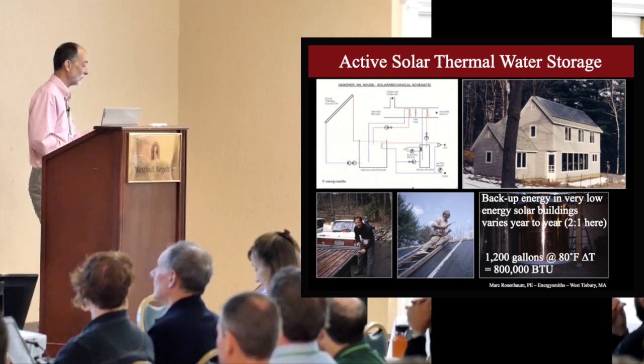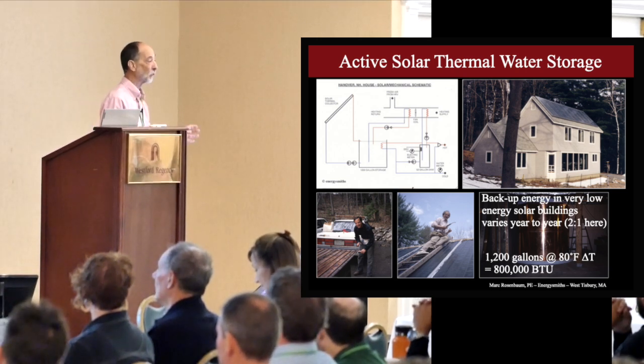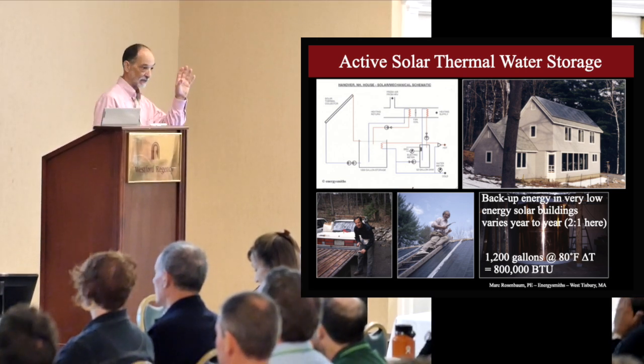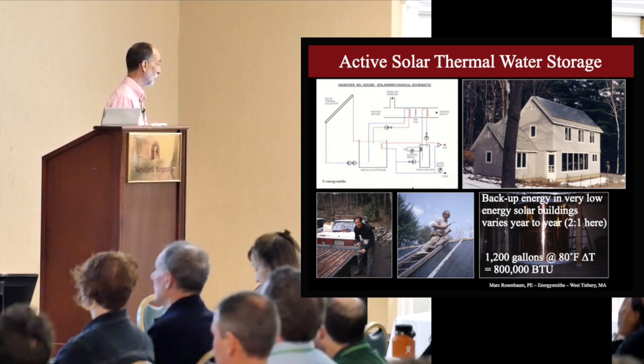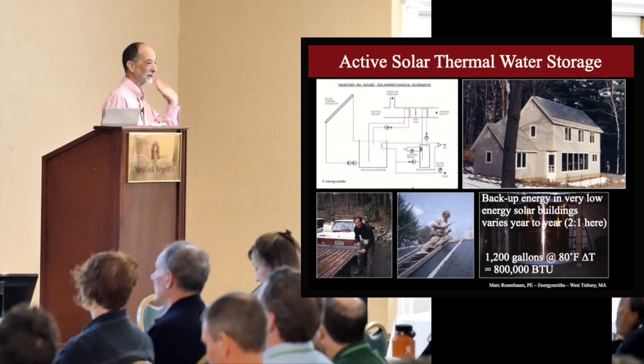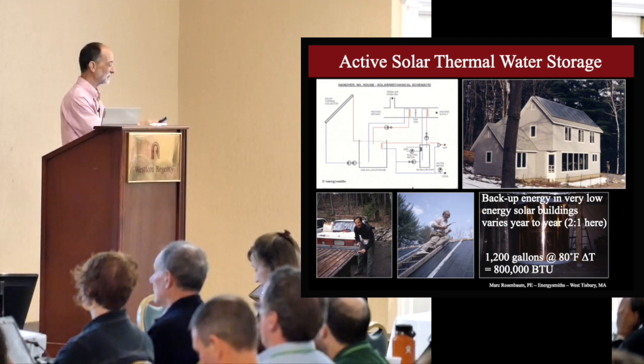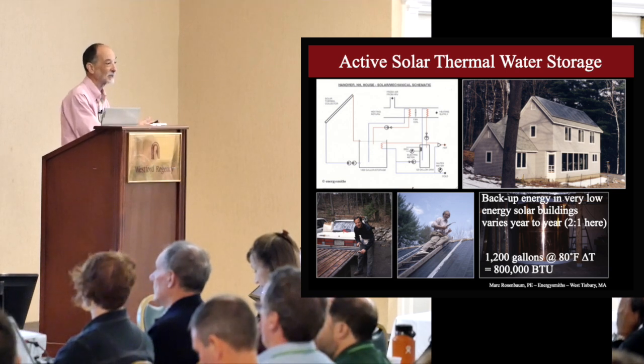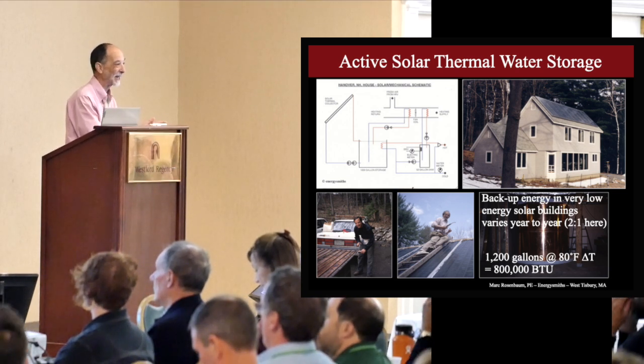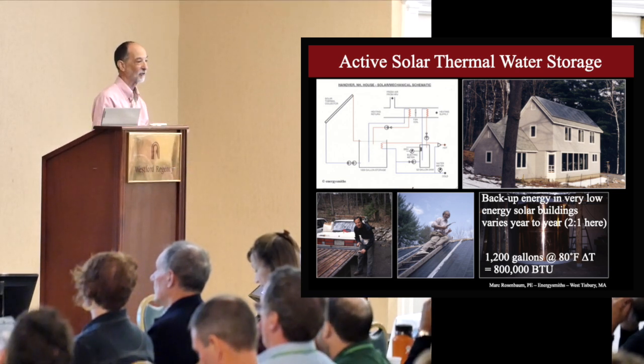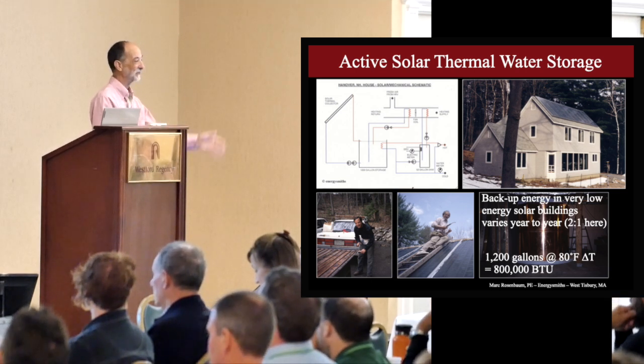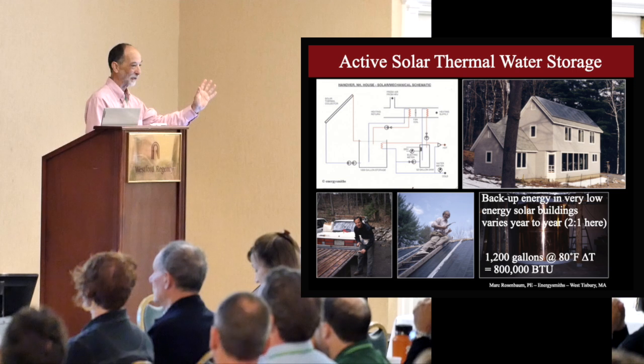So the backup heat is a 50-gallon electric water heater, and that water goes into the hot water coil. You can still pull energy out of it, both pumps can work at the same time, both coils can work at the same time, and you can pull that tank all the way down to 80 and still heat the house. You have to supplement it with the other coil if it's really cold.